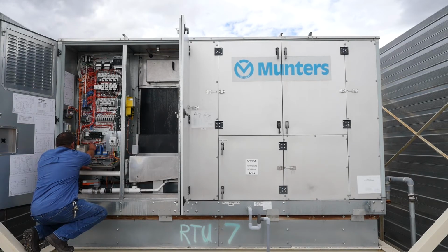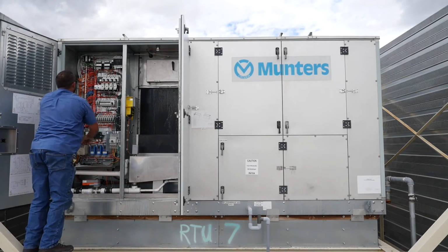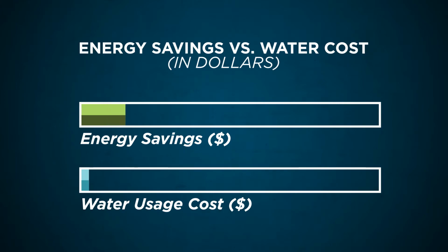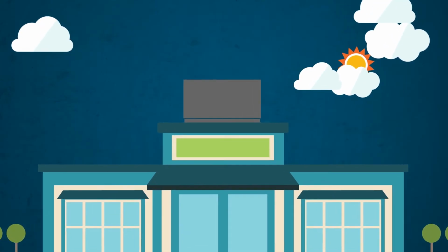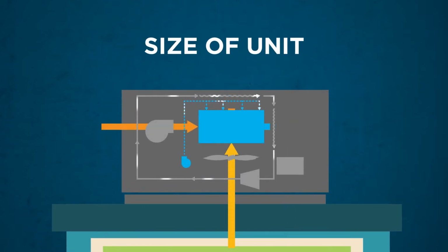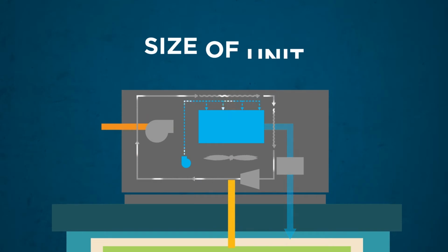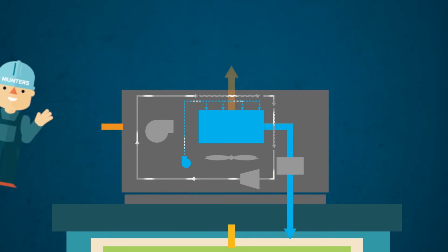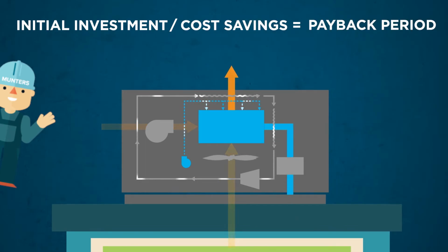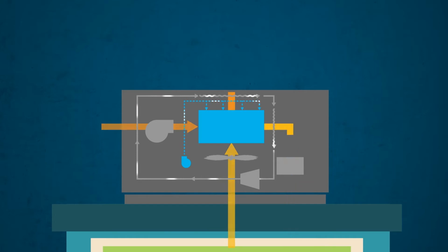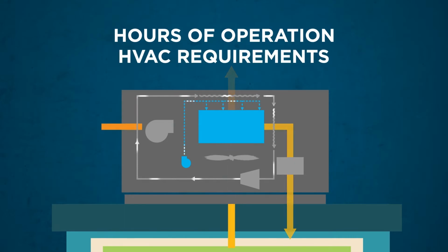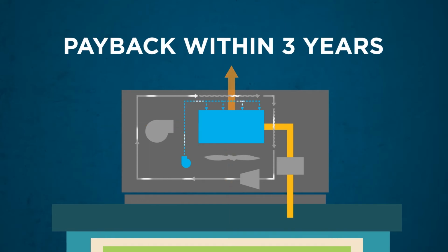Evaporative cooling technologies of today are designed to minimize water use and deal with a range of water supplies with varying quality. The money saved from reduced electricity consumption and peak demand can be used to offset the cost of the water used. The cost of a Munters EPX installation varies with the project details, including the size of unit, so we can't give a single cost estimate. But Munters sales and distribution channel partners work with potential customers to calculate the expected payback period before an investment is made. Of course, actual payback will vary in each circumstance, based on factors like hours of operation and the building's HVAC requirements, but many customers who have installed the EPX report payback in 3 years or less.